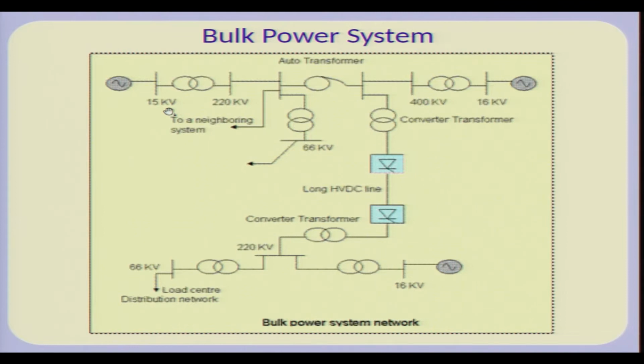It is a 3-phase system, and these are usually stepped up, and you have transmission at 220 kV or 400 kV. Although these are high voltage levels, 220 and 400 kV have a ratio of roughly nearly about 2. So, it is more economical to have connections using auto transformers rather than a complete two winding transformer. Auto transformers are more economical than typical 2-winding transformers because for lower transformation ratios there is an economic advantage.